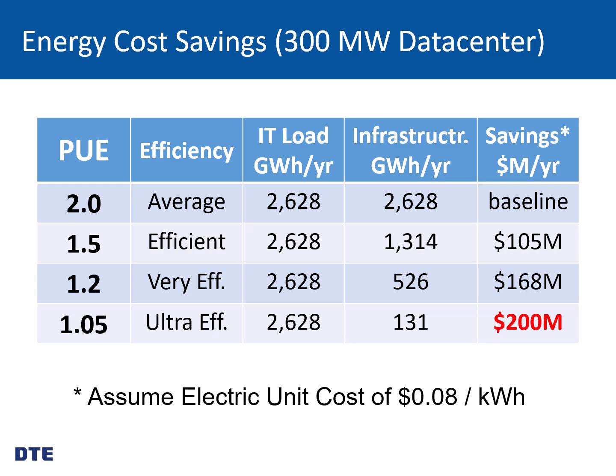Baseline, if you're using 8-cent power from your microgrid or local utility, a 2.0 PUE means a 300 megawatt data center uses 300 megawatts more of base load energy - that's the baseline in gigawatt hours per year. Drop that down to 1.5, and you save about $100 million a year. Drop it down to an ultra efficient system, and you'll add a lot of capital cost to get there - though maybe not as bad as it looks - but that's potentially $200 million per year in savings. If you're getting a great deal from your utility, paying only 4 or 5 cents, that erodes the savings, but this gives you an idea of the scale.